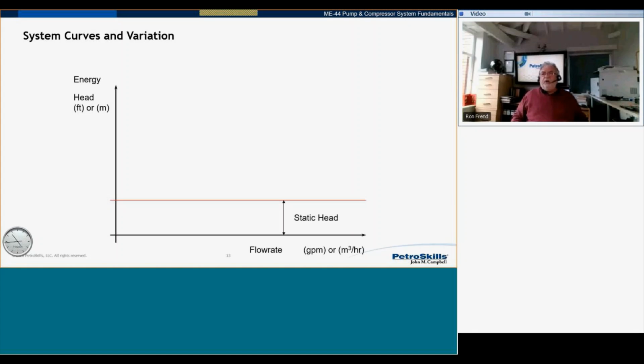First of all, I put a straight line on the bottom, which is the static head. The static head is what we call the elevation head and the pressure head. So this is the elevation head on the suction, looking at the elevation head on the discharge and looking at the difference. That's a total elevation head. I look at the pressure head on the discharge, the pressure head on the suction, look at the difference. That's the total pressure head. It does not change as the flow changes. So that's a straight line.